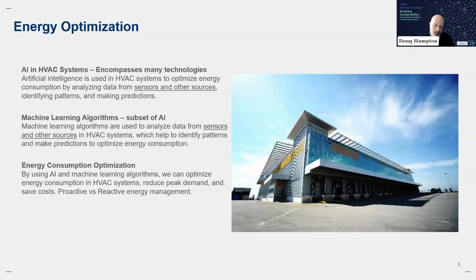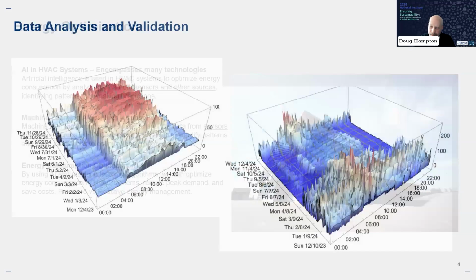By using machine learning algorithms—and that's something we hear a lot about, whether it's doing analysis, fault detection, things like that—anybody in the controls world knows what an algorithm is. Basically, most all of HVAC right now is reactive in nature, whether it's a critical zone reset, linear reset, or any demand or dynamically based reset—it's reactive. We see something happen and we react. AI is more of a proactive approach, and I'm going to show you a few examples of that here today.